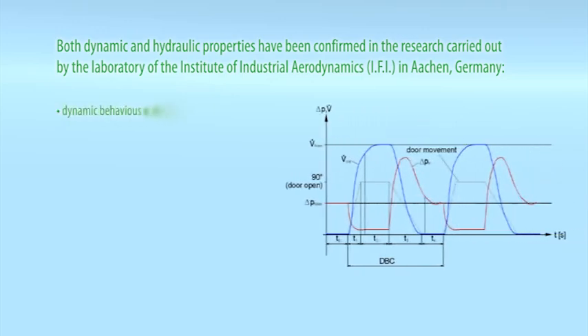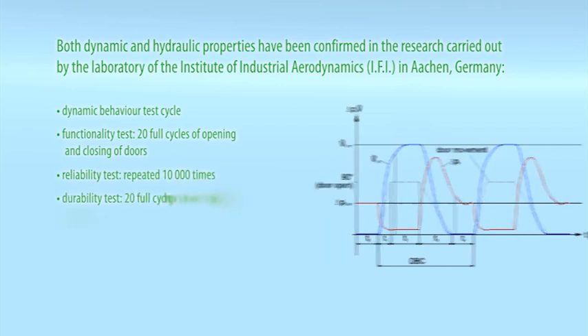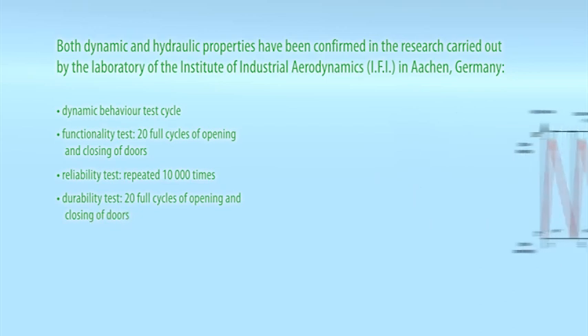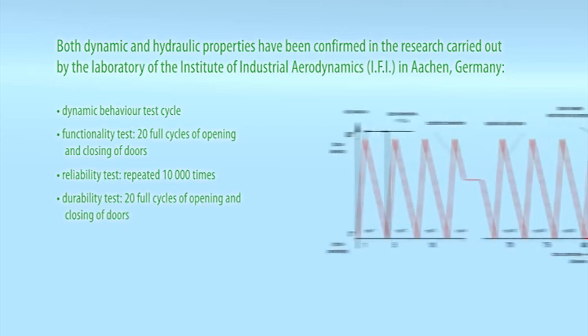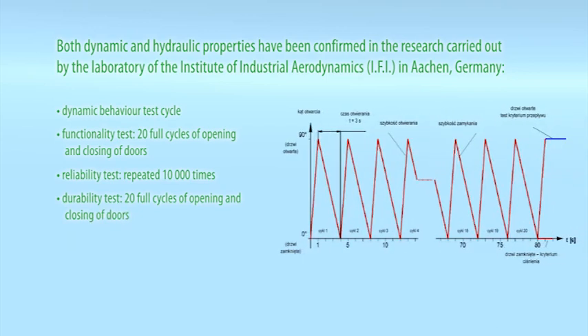Dynamic behavior test cycle, functionality test 20 full cycles of opening and closing of doors, reliability test repeated 10,000 times, durability test 20 full cycles of opening and closing of doors, resonance test 10 individual series of tests, 20 cycles each, all of them with open and closed air release opening.